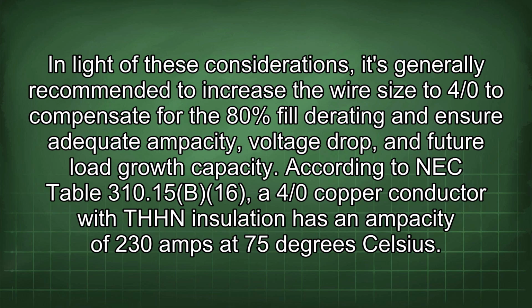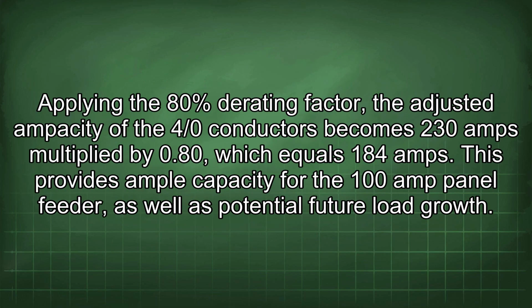According to NEC Table 310.15(B)(16), 4/0 copper conductor with THHN insulation has an ampacity of 230 amps at 75 degrees Celsius. Applying the 80% derating factor, the adjusted ampacity of the 4/0 conductors becomes 230 amps multiplied by 0.80, which equals 184 amps. This provides ample capacity for the 100 amp panel feeder, as well as potential future load growth.